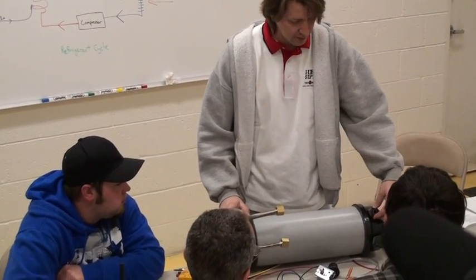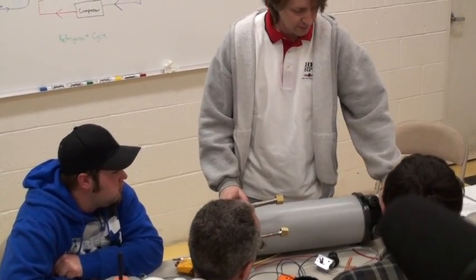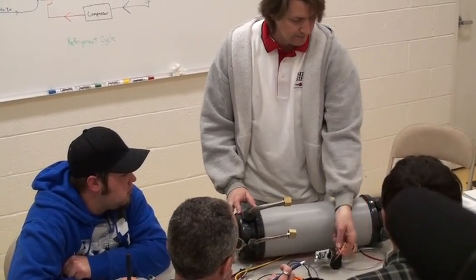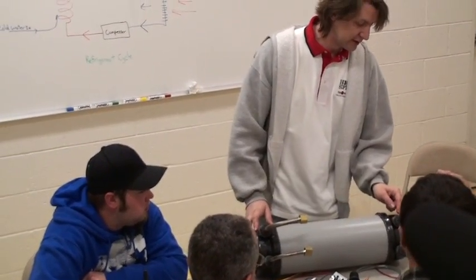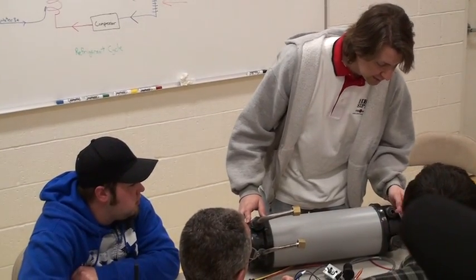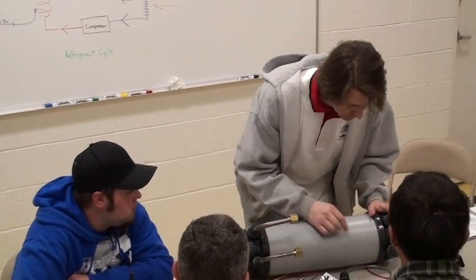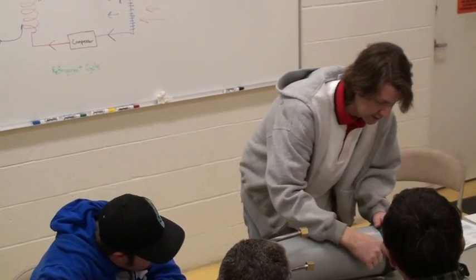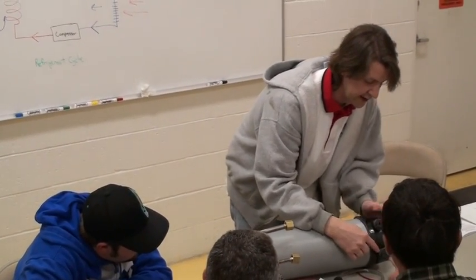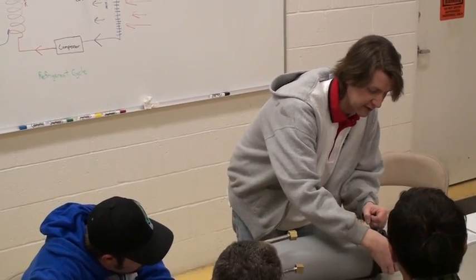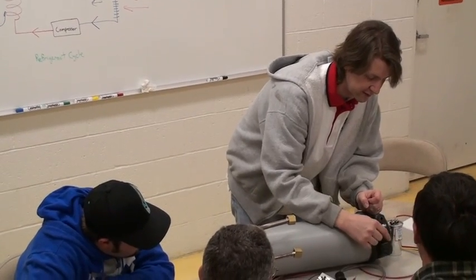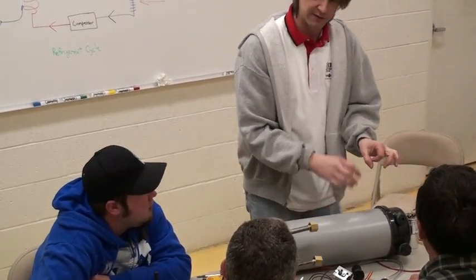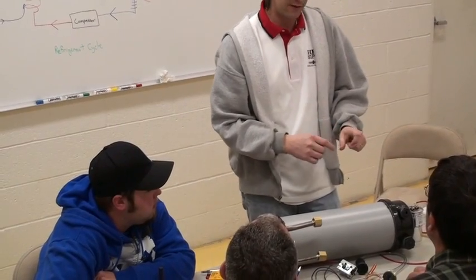These fittings are unavoidable. This is the water pressure switch fitting and the temperature sensor. There's actually two pieces. This one's probably the easiest one to see. There's this larger hex here, it's glued in. And then that provides threads. And this is a compression fitting. If I were to undo this, these sleeves and these two pieces, I'd have a little piece of Viton tubing.